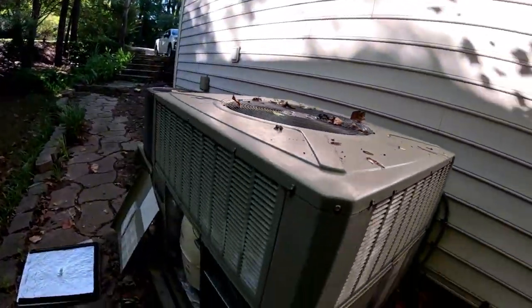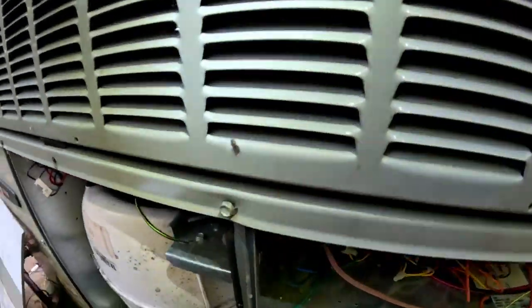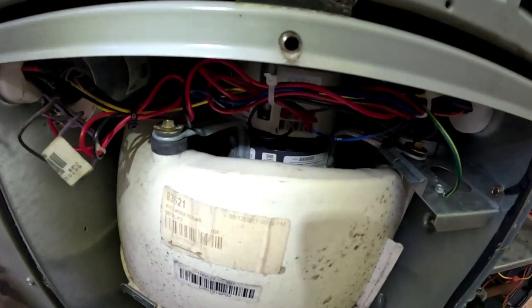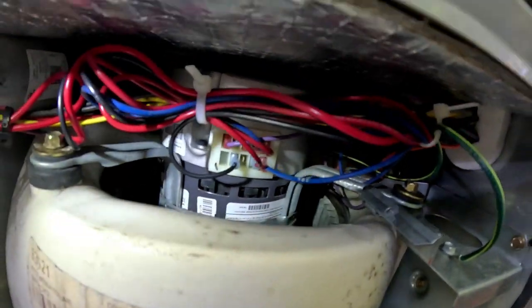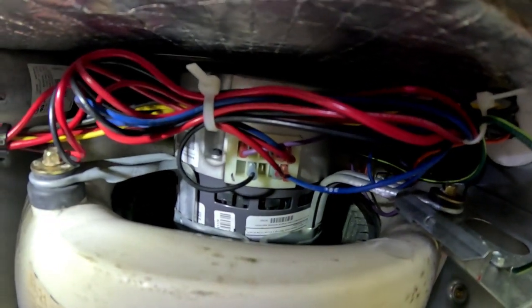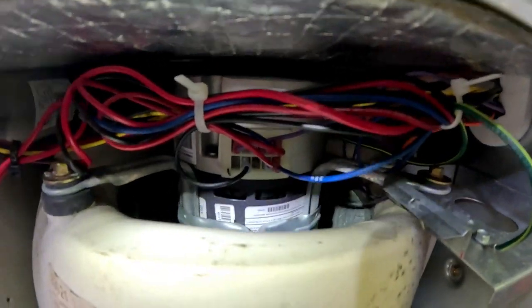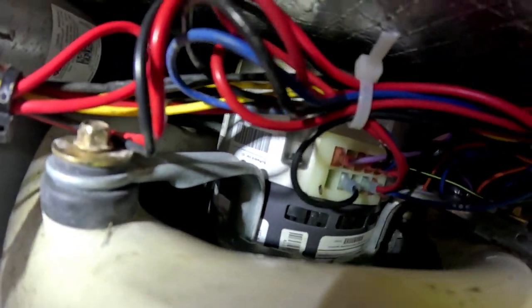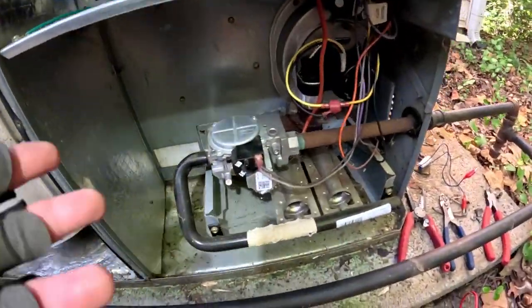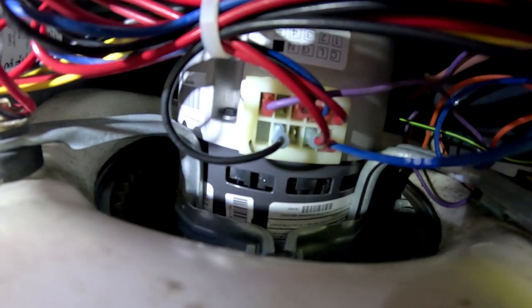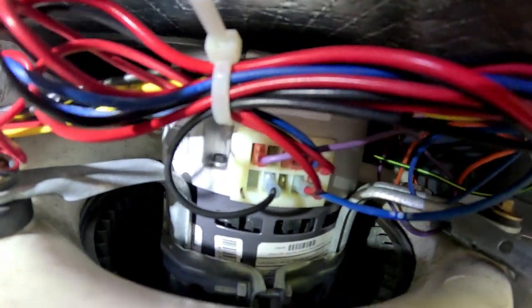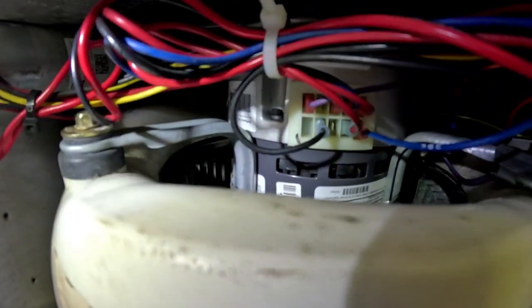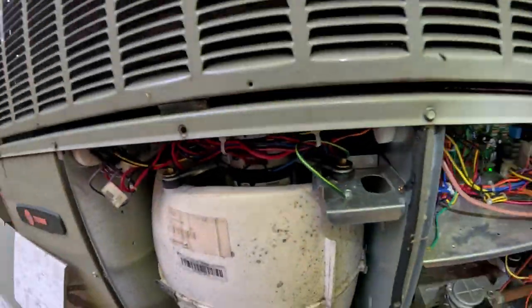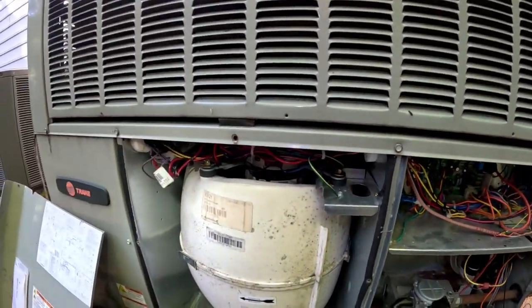I'm still going to recommend replacing it because, I mean, it is what it is. Just can't guarantee after something's been shorted like that, especially these things, what kind of life he's going to get out of it at this point. It looks newer. It's not as dirty as the unit, and that motor doesn't look like it's all that old. Maybe it's been replaced before and whoever put that in didn't zip tie the wires back up. I don't know. But anyway, he did say he's had that replaced recently.